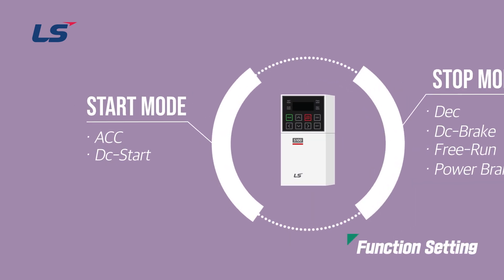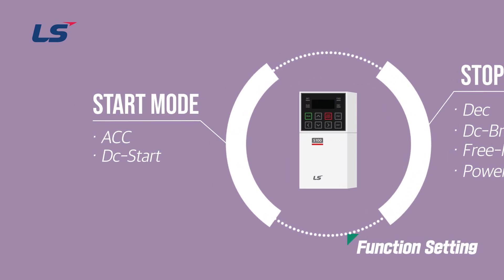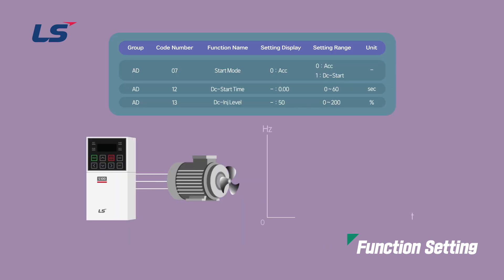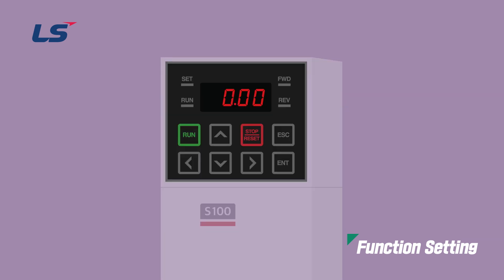Let's see how to set the start method. The ACC acceleration start method is a general acceleration method. If no other function is selected, the AC drive will accelerate to the target frequency by reflecting the acceleration time when the operation command is input. Set by selecting 0 ACC in start mode AD7.